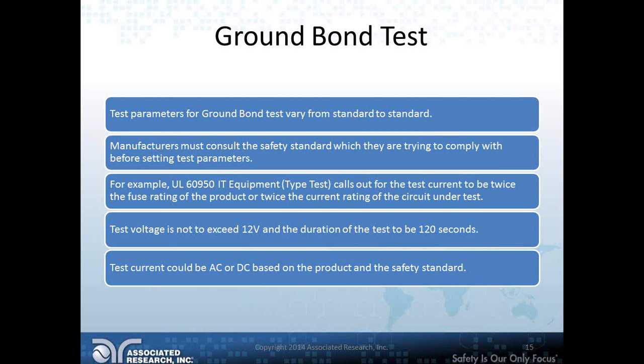The test voltage must not exceed 12 volts, and the duration should not exceed 120 seconds, since this is a high current test. The test current can be AC or DC depending on the product and safety standard — for example, solar panels may require DC ground bond testing.